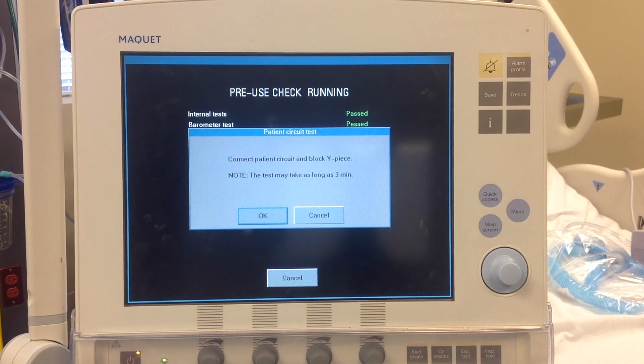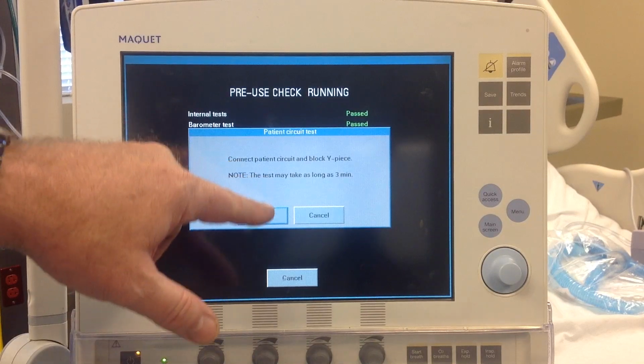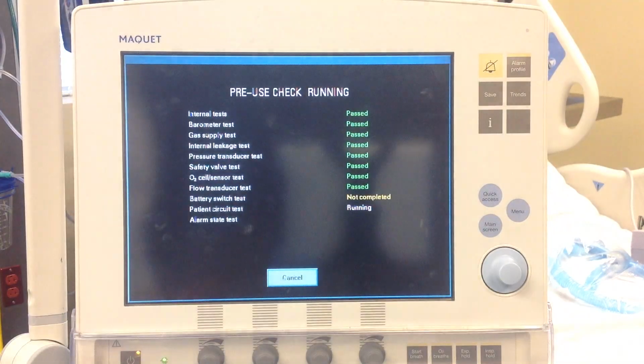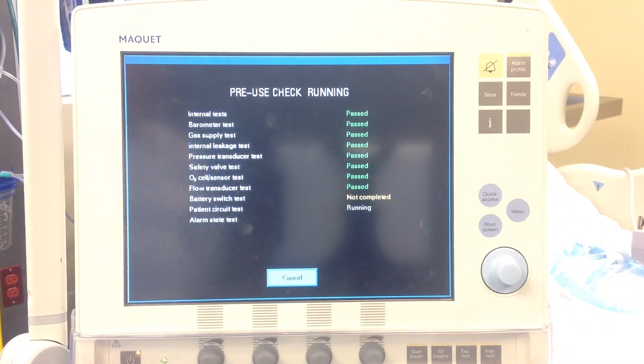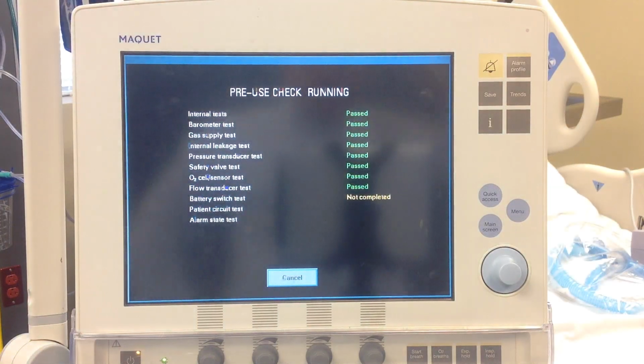But the problem is your expiratory cartridge does not have a filter at all. So therefore anything coming out of the patient's lungs, you are breathing it. So connect the patient, or connect it. I've blocked the Y. Where it said battery switch test and it says not completed, the only thing it would have you do is, if our batteries were good, it would ask you to unplug the ventilator from the wall so it could actually test the batteries and see how long they would last.